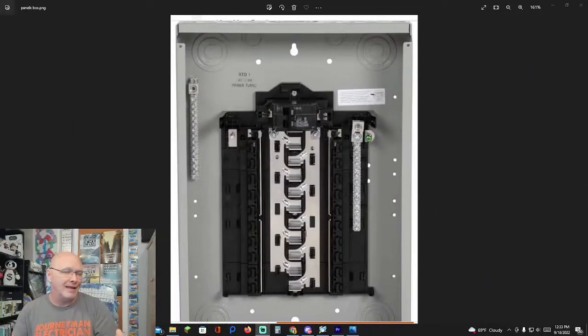So to understand how the breakers are going to work and how I'm going to connect this, I want to explain a little bit about a panel box. So this is your standard residential single-phase panel box. It's got your main disconnect breaker here. It's got your neutral bus bar here. And it's got your ground bus bar over here. And then you have your two phase plates, which will connect here and run down this guy. And this phase plate will have 120 volts. Your next one will connect here and runs down this way, and it has 120 volts on it.